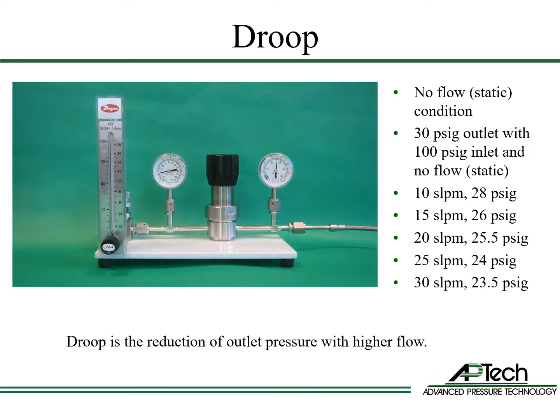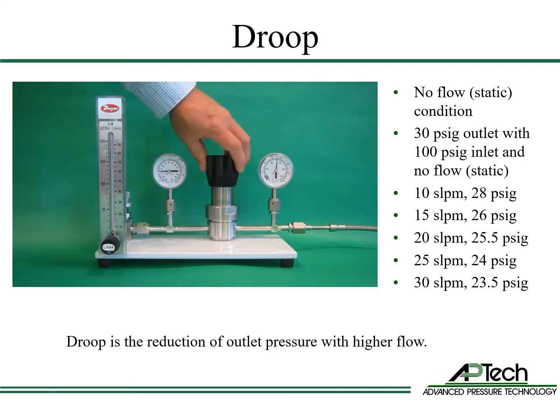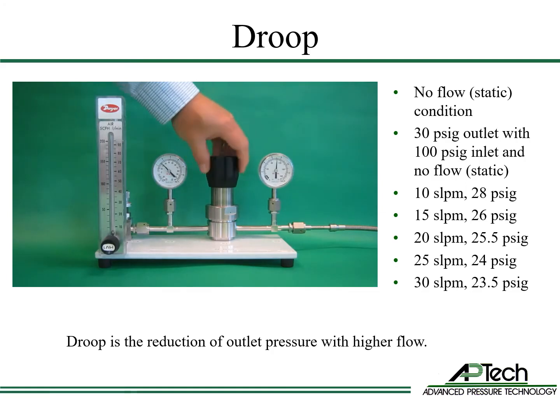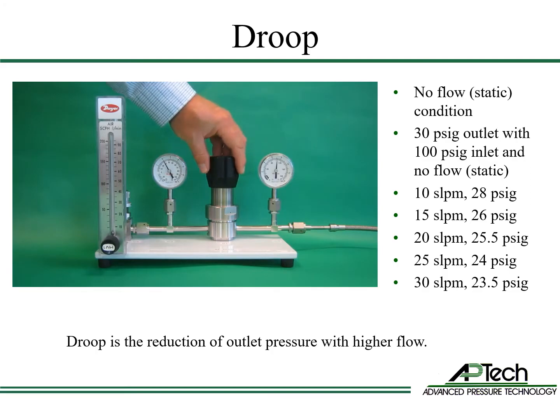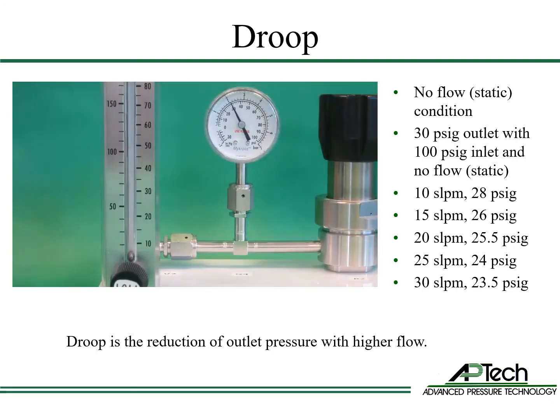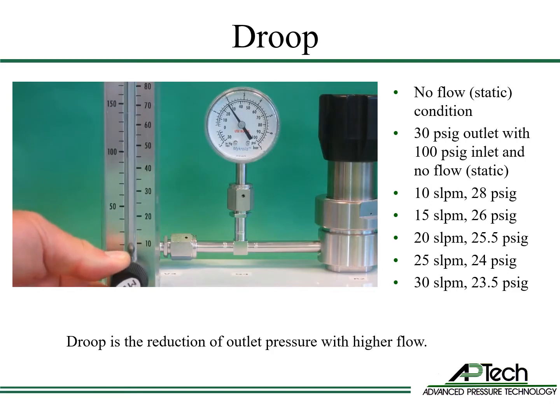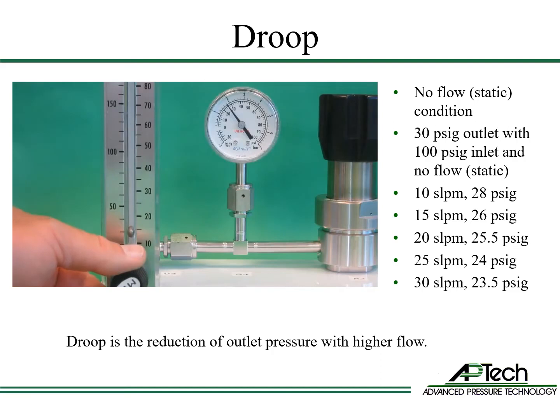Droop is the reduction of outlet pressure with flow. In this example, an AP1000's inlet pressure is set to 100 psi. The regulator is opened and adjusted to 30 psi outlet pressure with no flow. As flow begins, the outlet pressure drops. At 10 liters per minute, the outlet pressure droops to 28 psi.